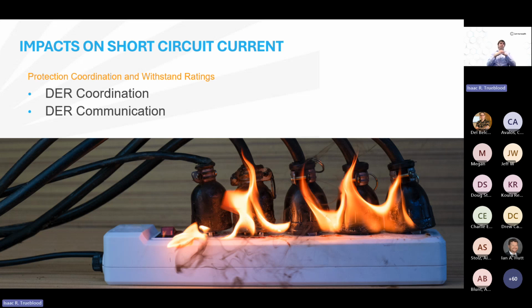One way is for distributed energy resources to simply trip offline, like any other generation site, when a fault is detected or there are grid irregularities. This would prevent distributed energy resources from supplying faults with the increased fault current and prevent unstable microgrids. However, that is easier said than done.